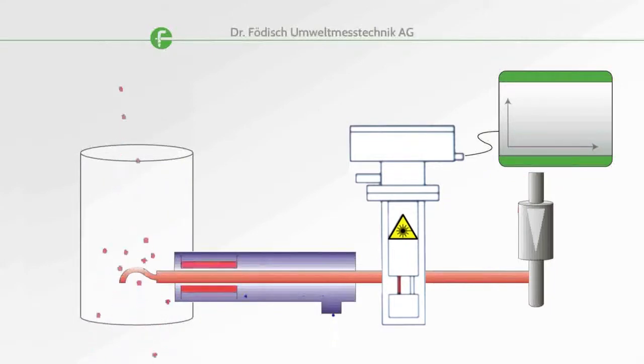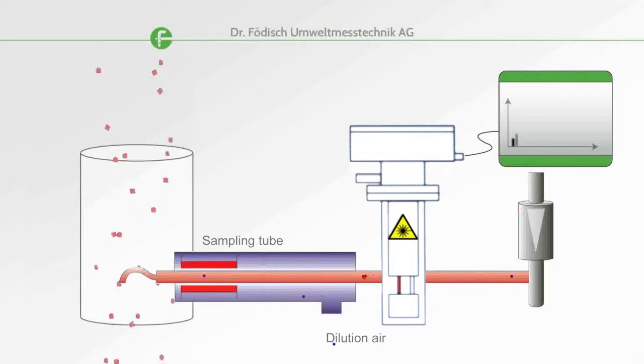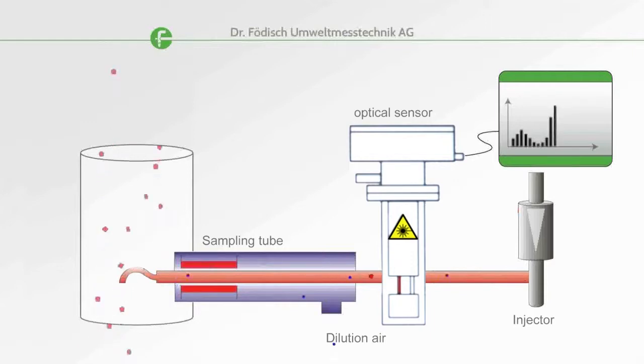The probe extracts measuring gas from the exhaust gas stream. Preheated dilution air is added. The resulting mixed gas is heated at a defined temperature within the sampling tube. The injector sucks the measuring gas through the measuring chamber, having the optical sensor inside. Its measuring values are compensated by the measuring values for temperature and flow. The control unit shows the dust concentration in milligrams per cubic meter in operation.